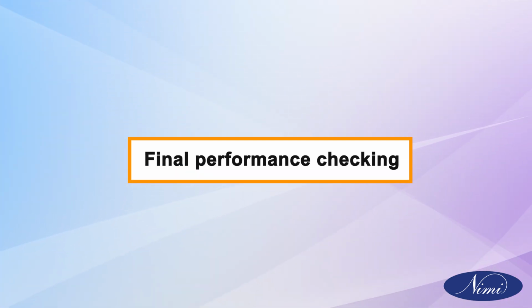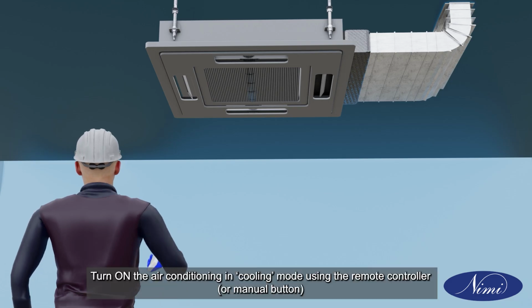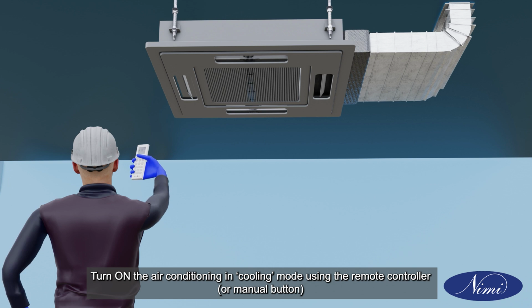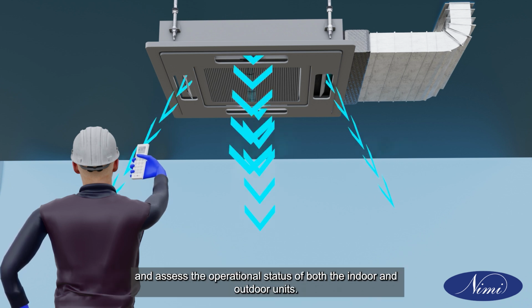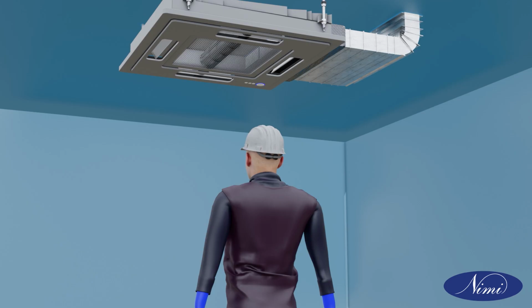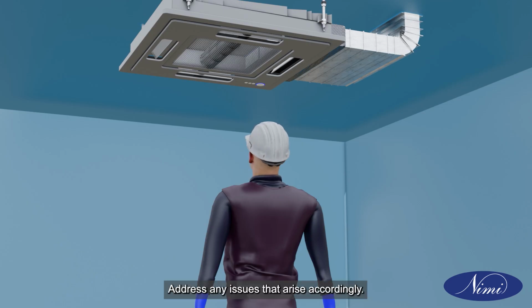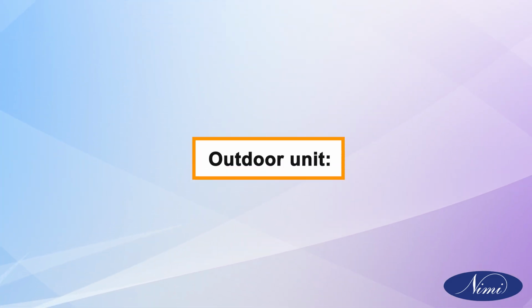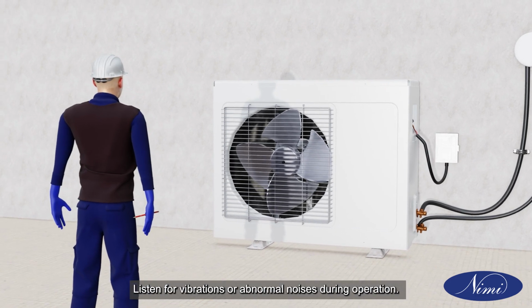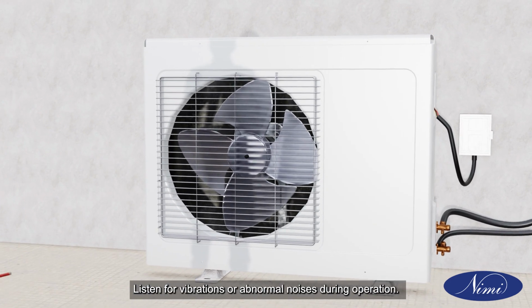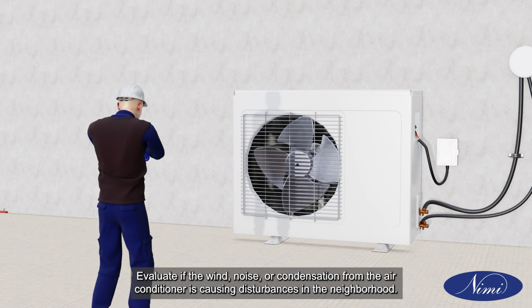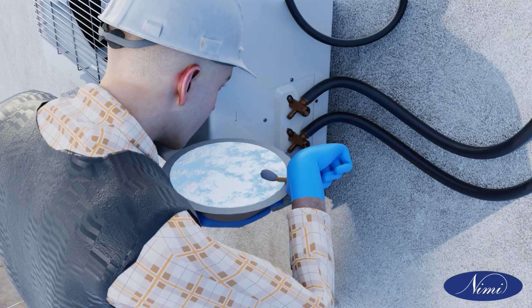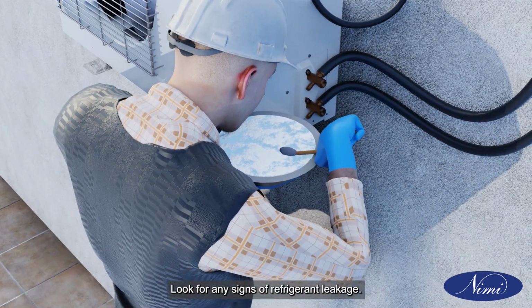Final performance checking. Turn on the air conditioning in cooling mode using the remote controller or manual button and assess the operational status of both the indoor and outdoor units. Address any issues that arise accordingly. Outdoor unit. Listen for vibrations or abnormal noises during operation. Evaluate if the wind, noise, or condensation from the air conditioner is causing disturbances in the neighborhood. Look for any signs of refrigerant leakage.